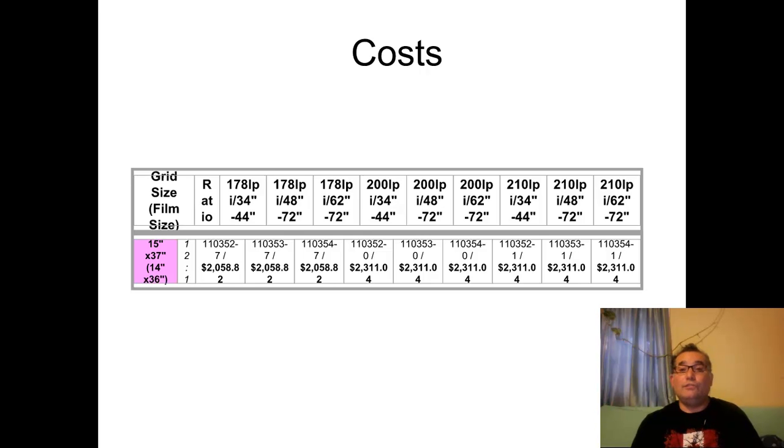Conversely, lower grid ratios have a larger space between the lines, which allow for more positioning latitude. But the trade-off is they don't clean up scatter as well. So I hope you found that interesting. Unfortunately, we need to use grids despite the fact that we are increasing the dose to the patient.